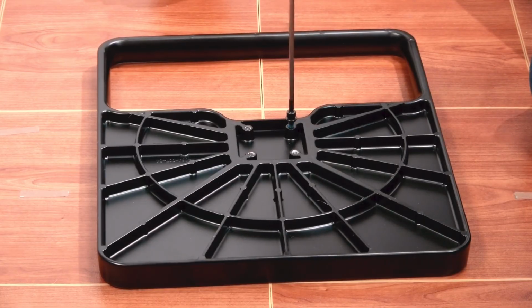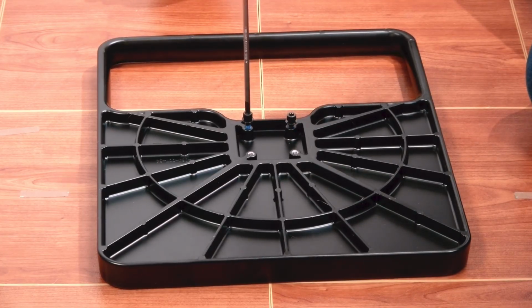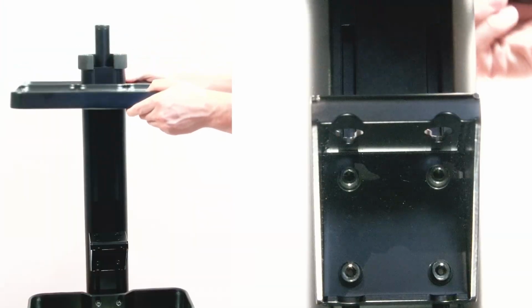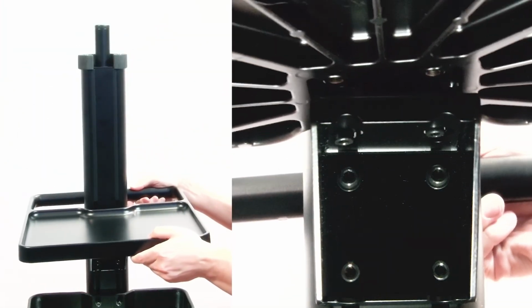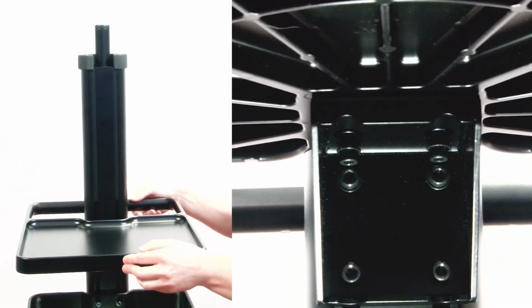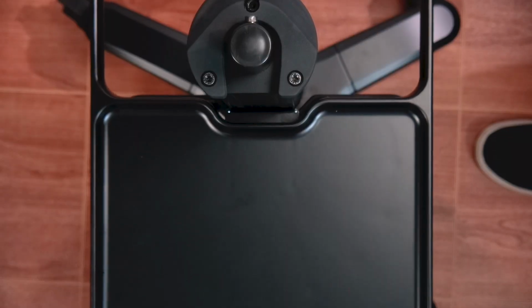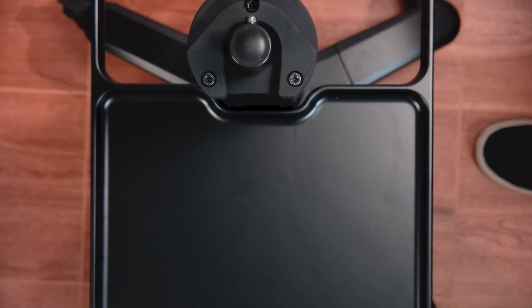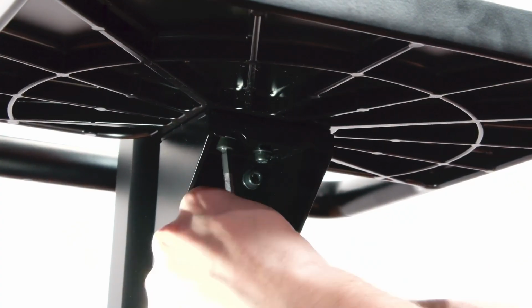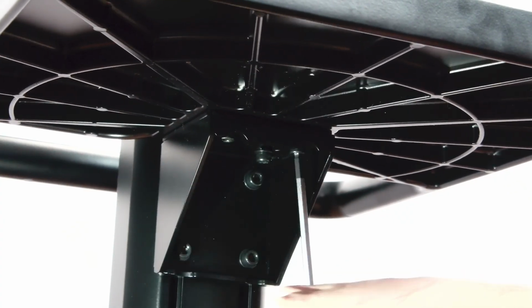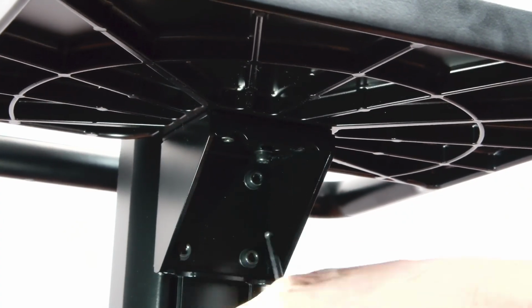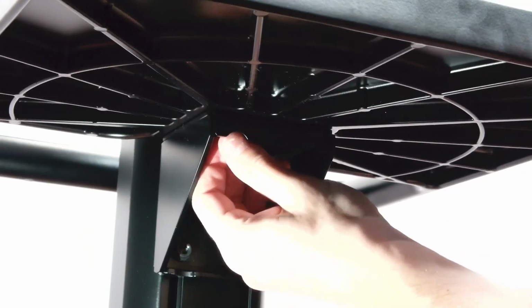Partially install 2 M6 by 15mm screws about 2/3 of the way into the 2 holes closest to the handle on the bottom of the tray. Then slide the tray over the column, aligning the screws with the slots on the tray bracket. Secure the screws within the slot by pushing the tray flush to the column. Install 2 more M6 by 15mm screws into the second set of holes on the tray and fully tighten all 4 screws.